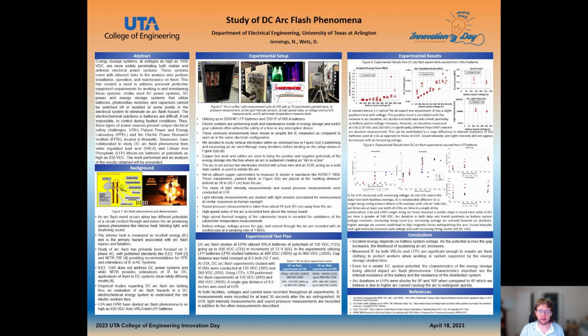At UTA, DC arc flash experiments studied with VRLAs were conducted at 130 volts DC and 260 volts DC. Using LFPs at UTA, we performed arc flash experiments at 120 volts DC up to 480 volts DC, using a single gap distance of 0.5 inches. At both facilities, voltage and current were recorded throughout all experiments. Incident energy measurements were recorded for at least 30 seconds following the arc to allow for any residual heat to soak into the copper calorimeters to measure.